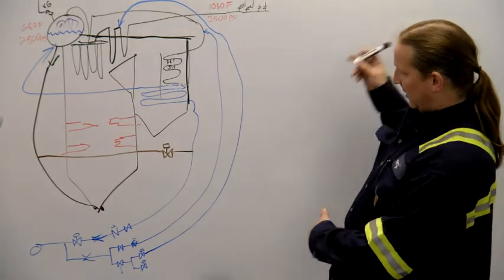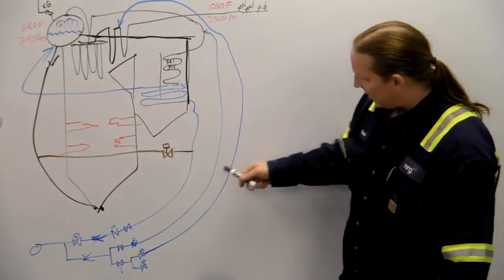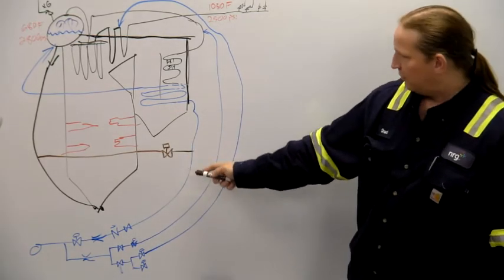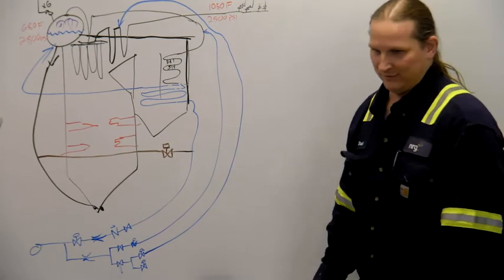Once we sync and we know we're going to have steady feed water flow through this all the time, we quit worrying about that and we shut the recirc valve so that we get as much preheat out of the water as we can.